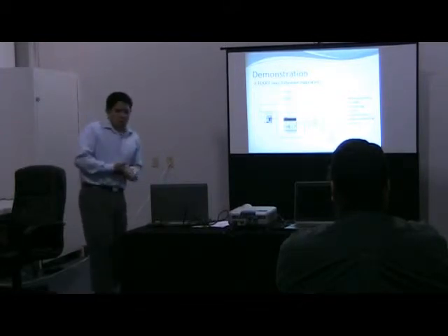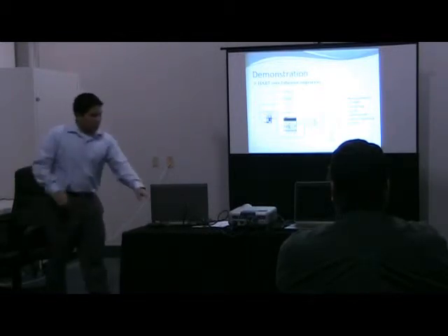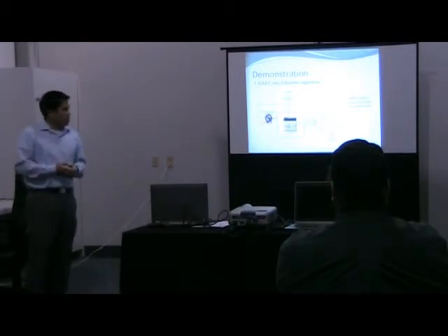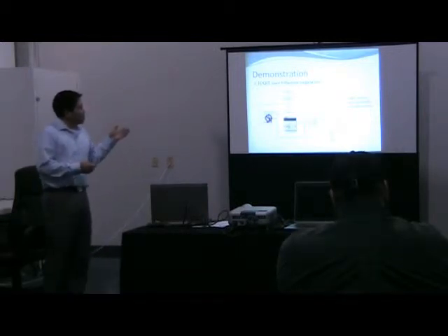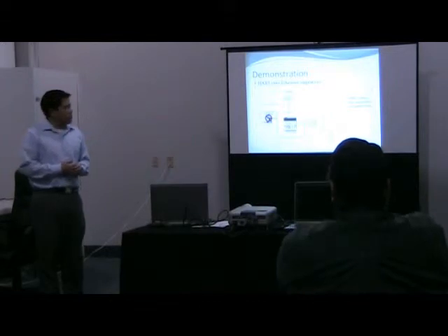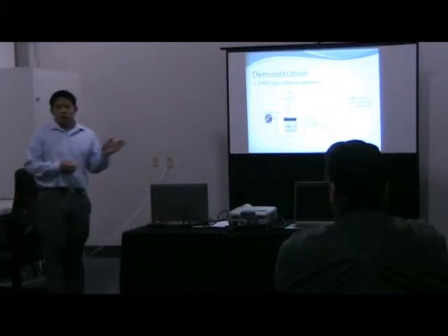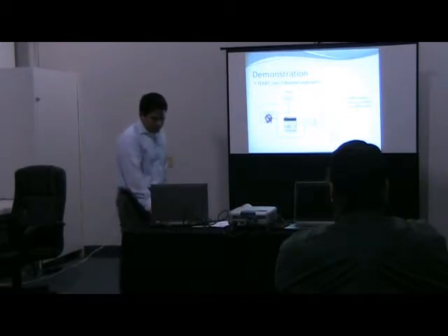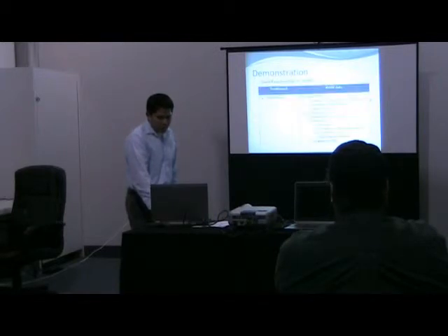And so to go over some of the common concerns that we had again. If the modem goes down, we don't impact the process. The instrument techs can still troubleshoot the device like they normally do. And we could possibly install this while the process is running. We didn't have to break any wires. So here are the issues that we resolved.